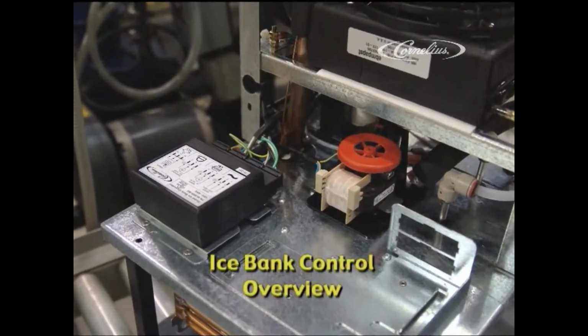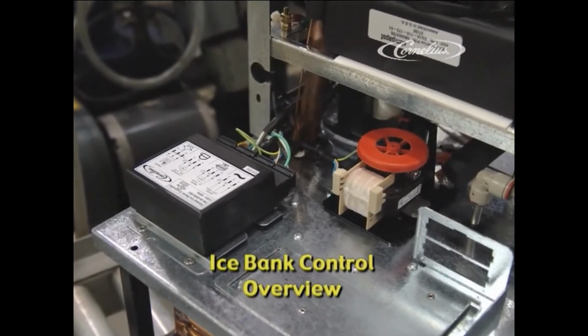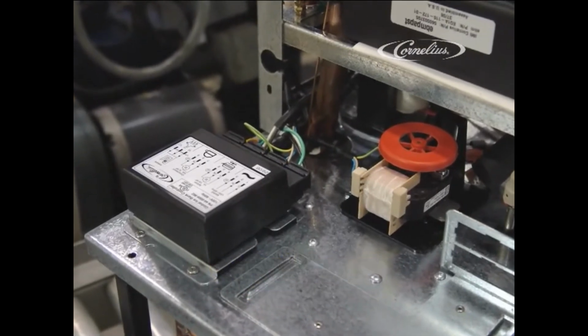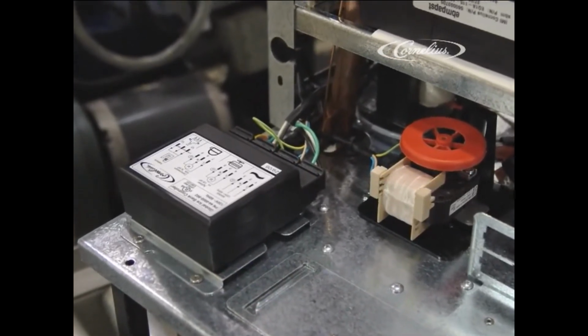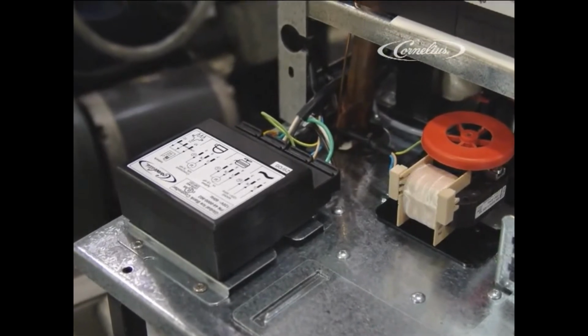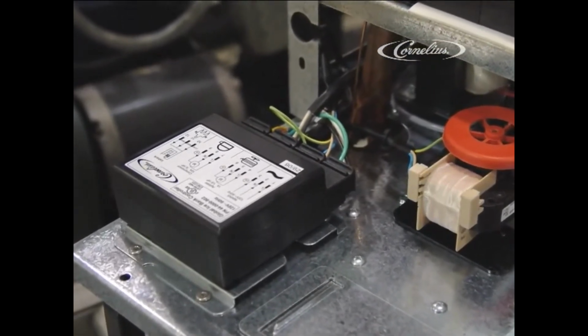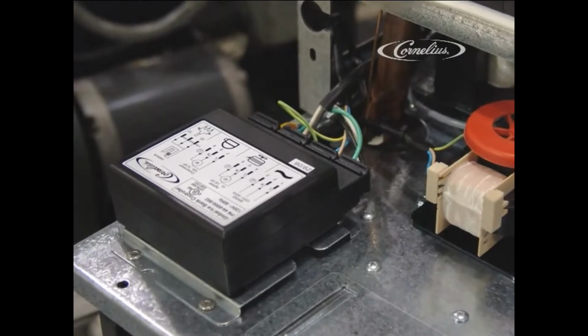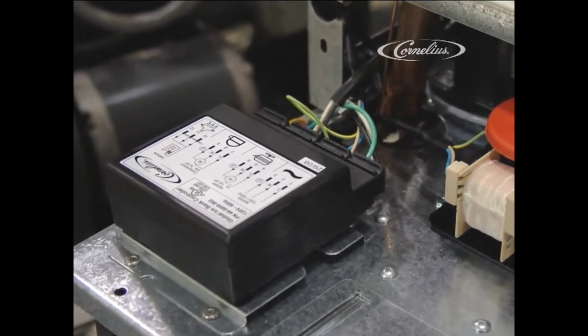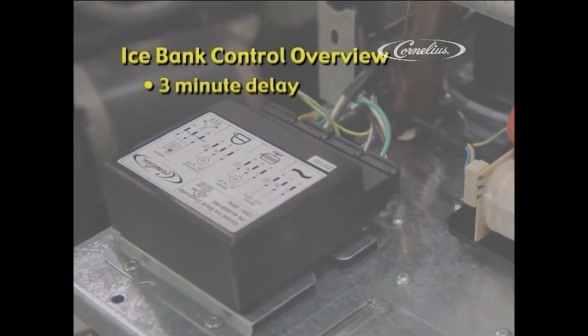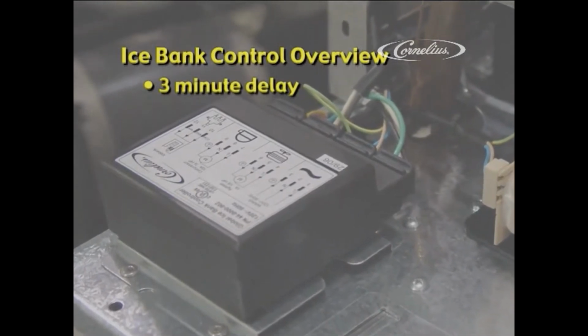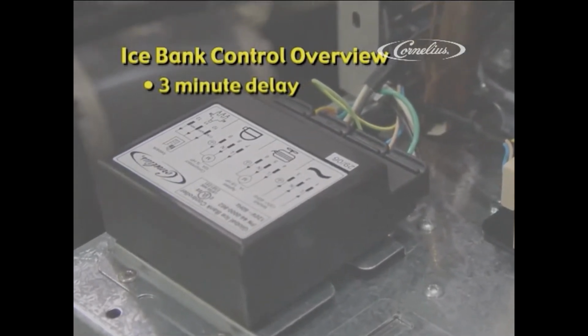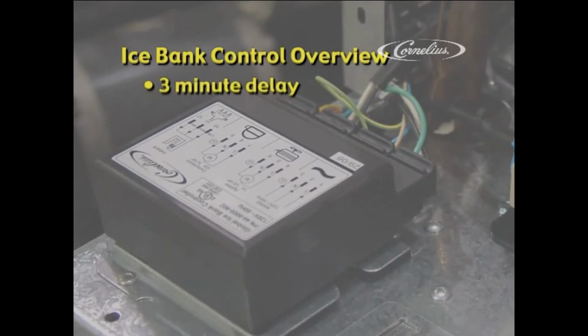The IBC, or ice bank control, is a solid-state design that, by means of a probe assembly that is strategically located in the water bath, controls the refrigeration on and off cycle time. It accomplishes this by being able to sense the resistance difference between plain water and ice. The control has a built-in 3-minute delay before calling for the compressor to activate. If there is any interruption in power to the dispenser, whether it's unplugged or if the incoming power to the building is interrupted, the system will wait the 3 minutes before activating the refrigeration system.